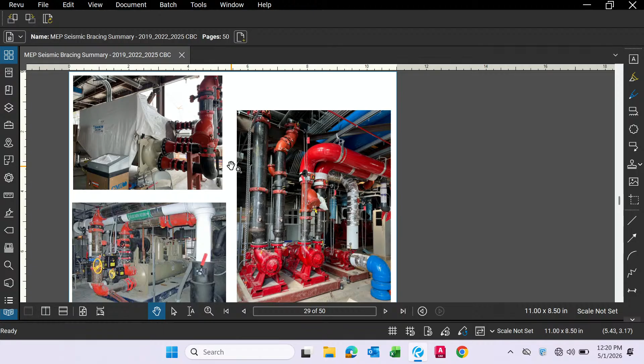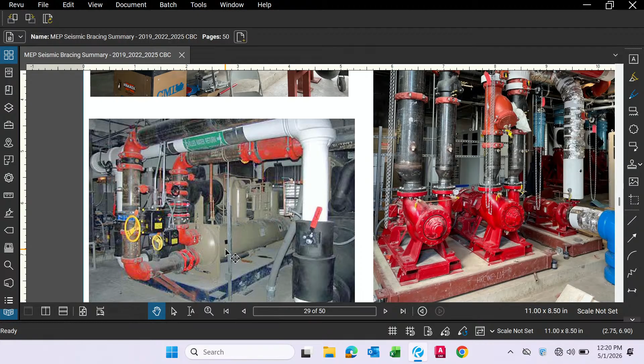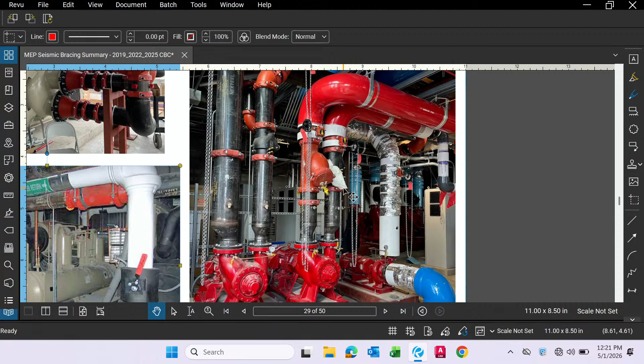I think what happened is somebody forgot to design support for the pipe elbow here, so they tied it back to the base. You can see there's a flexible connector there, so that locks it up, which defeats the purpose. And on this side, this one has nothing - no flexible connectors there. So it's going to have the same type of failure you saw in the earlier photo.